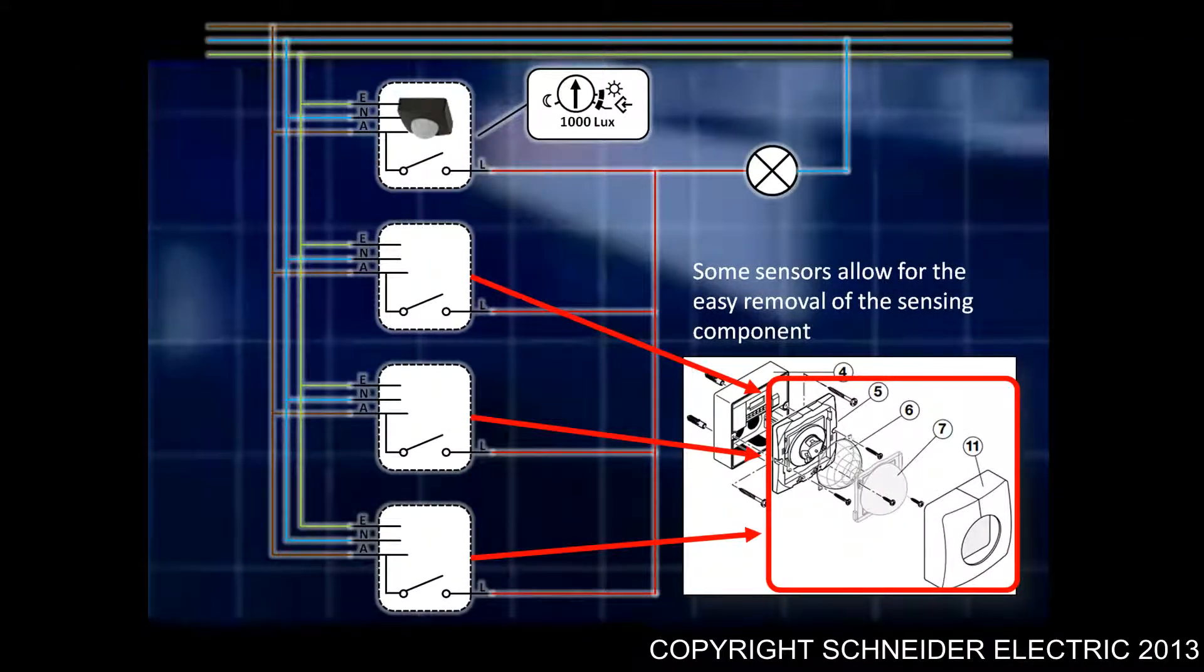The best way of fault-finding multiple circuits, if you suspect incorrect programming, is by removing all of the sensors but leaving one. Program that sensor up as you normally would and test the functionality. Some of the Clipsal sensors have a removable sensor head, which allows for testing to be relatively easy.